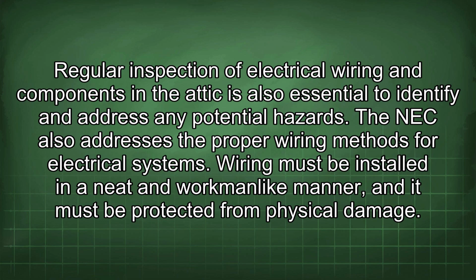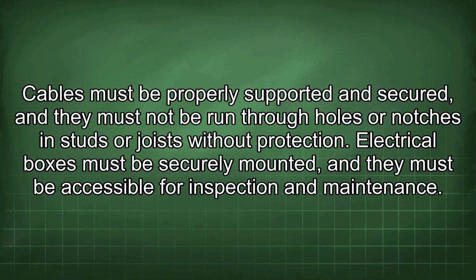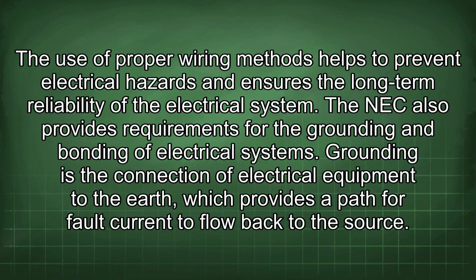The NEC also addresses the proper wiring methods for electrical systems. Wiring must be installed in a neat and workmanlike manner, and it must be protected from physical damage. Cables must be properly supported and secured, and they must not be run through holes or notches in studs or joists without protection. Electrical boxes must be securely mounted, and they must be accessible for inspection and maintenance. The use of proper wiring methods helps to prevent electrical hazards and ensures the long-term reliability of the electrical system.